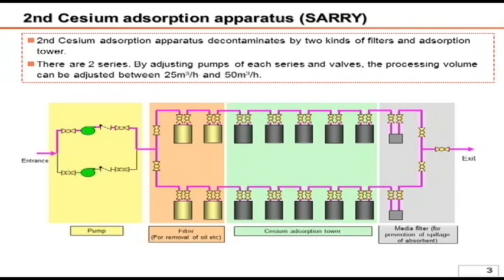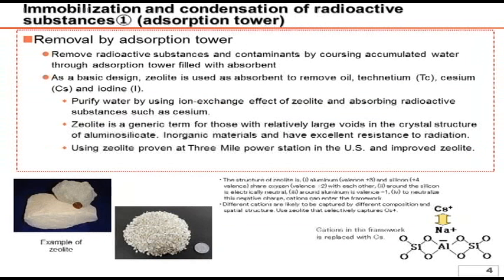Being the same as Kurion's system, SARI has two vessels in line which remove oil and impurities. Next, four vessels out of five absorb cesium. Lastly, the media filter — a small filter processes the water in order to prevent absorbent leakage. Different from Kurion, SARI has fewer dynamic parts, namely pumps. Hence, at the moment, we feel that SARI is superior to Curion in terms of operational reliability.